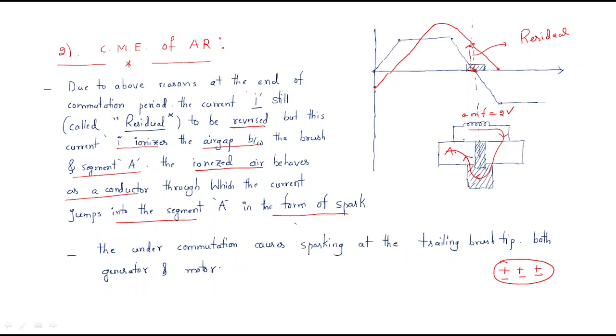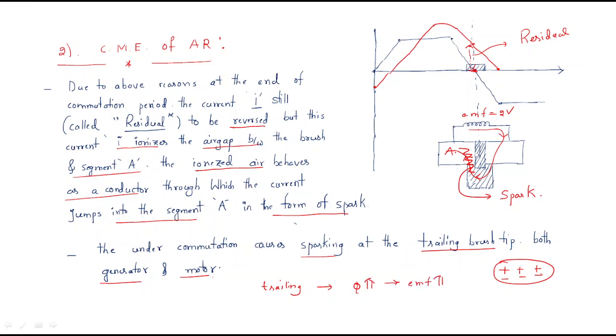Due to this, some spark is generated at segment A. The under-commutation causes sparking at the trailing brush tip in both generator and motor. This occurs at the trailing brush because the flux value is high there — high flux means high generated EMF, which causes sparking in both the generator and the motor.